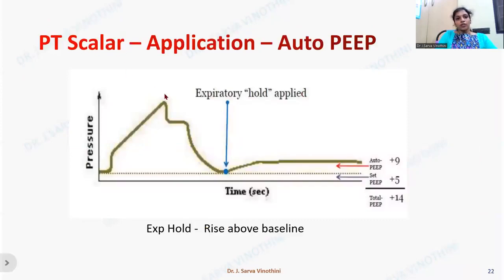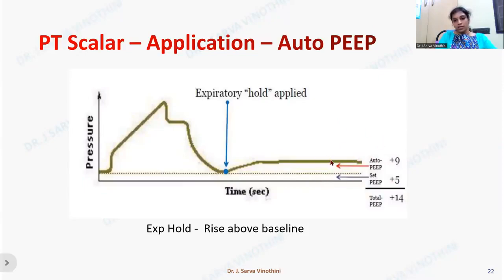Another application of the pressure-time scalar is determining auto-PEEP. Pressing the inspiratory hold button reveals plateau pressure. Pressing the expiratory hold button shows any pressure above the set PEEP — that excess is the auto-PEEP, representing air trapped in the lung that generates extra pressure above the set PEEP level.